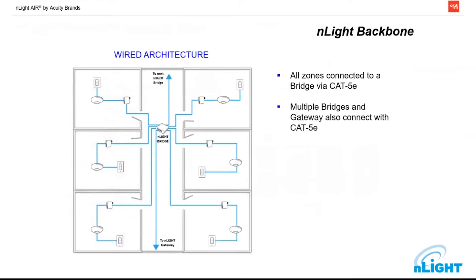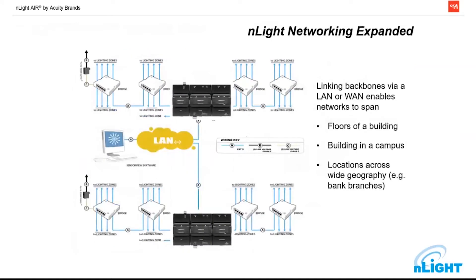Going even deeper, we add backbone devices. This is an example of a hallway with six classrooms or offices. We've created a little zone in each one, and we have essentially a bridge or router out in the hallway where we can pass information upstream and downstream. This ties it all back in and creates a little network. Adding the Eclipse module, we can now network multiple buildings across an entire campus. We can create schedules, show floor plans, and set different profiles. So it's very scalable from something as small as one room, one switch, one light fixture, all the way up to a building-wide or campus-wide system.